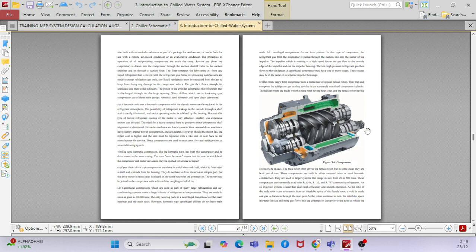So what we do normally when we are working on a project: we do the calculations, then we prepare our schedule, then we send it to different manufacturers. You require power, you require the sizes of the chiller, and you require different details. You send the details to the four manufacturers and get all the information. Then you validate all four, and based on that, you write your specification.